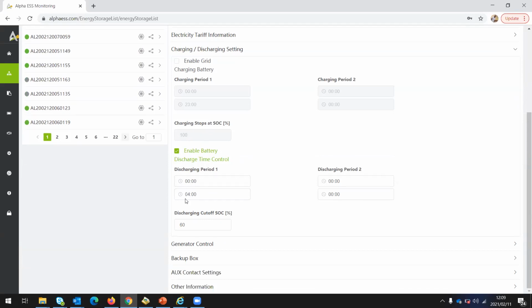Usually we don't recommend putting up this setting, because once you do so, if you have load shedding, the system will not supply your loads. So usually we prefer you leave the setting set to zeros and deactivate it, such that the system can discharge throughout the day. And then on discharge cut-off SOC, this is the reserve SOC, so you can change it remotely to whatever percentage you want. As I've said, this system is set to reserve 60% of the battery.